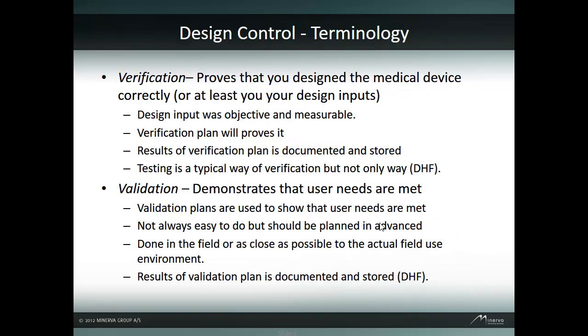The last two terms to introduce are verification and validation. Although they sound similar and are often misused, verification relates to design inputs, while validation typically relates to user needs. Regardless, they both are plans proving that the design input or user need is met. Careful consideration of how to validate and verify should be done as early as possible. The results of the validation and verification should be captured and stored and belong to the design history file.